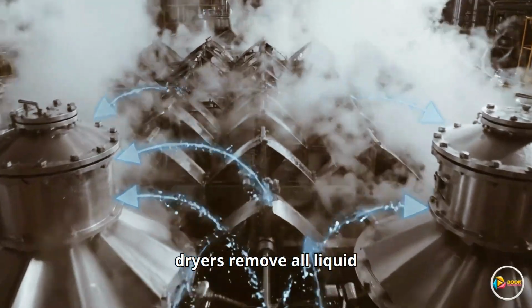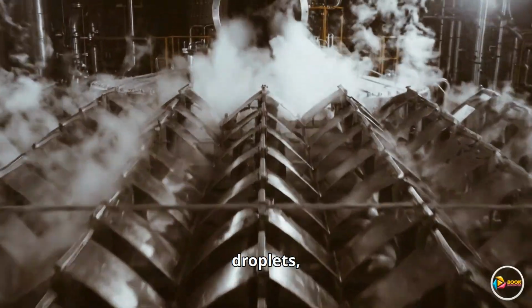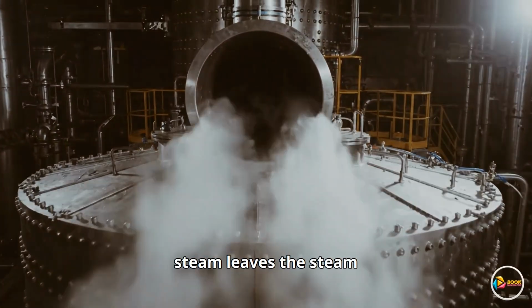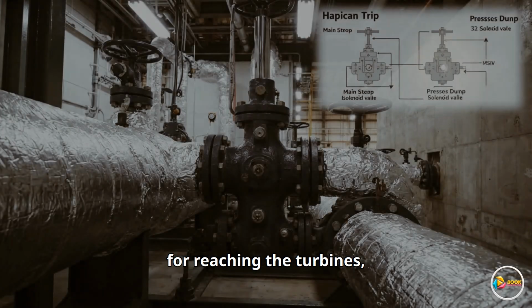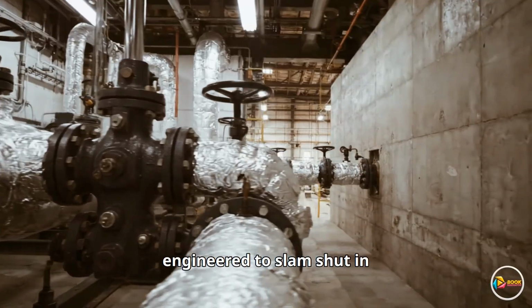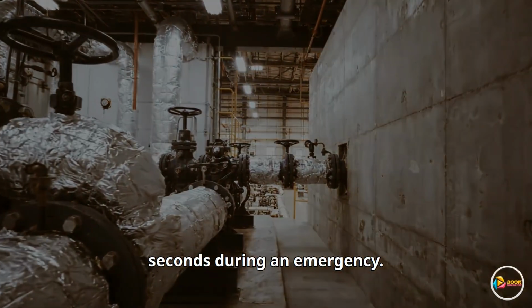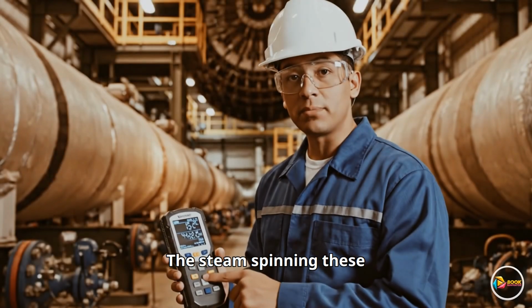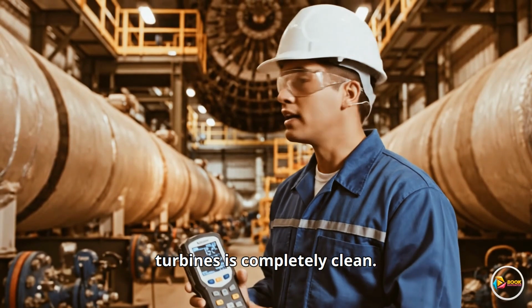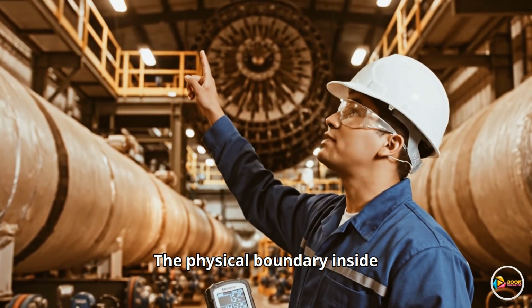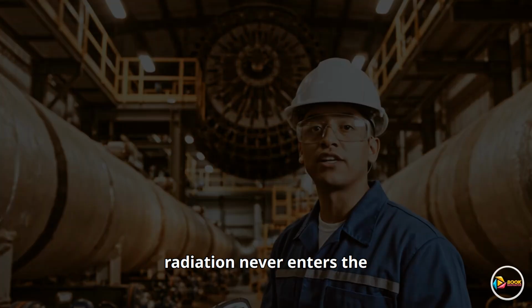Cyclone separators and chevron dryers remove all liquid droplets, ensuring that only bone-dry steam leaves the steam generator. Before reaching the turbines, the steam lines pass through rapid-acting main steam isolation valves, engineered to slam shut in seconds during an emergency. The steam spinning these turbines is completely clean. The physical boundary inside the steam generator means radiation never enters the turbine.